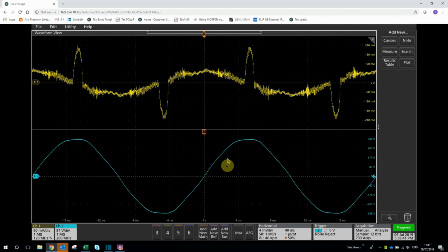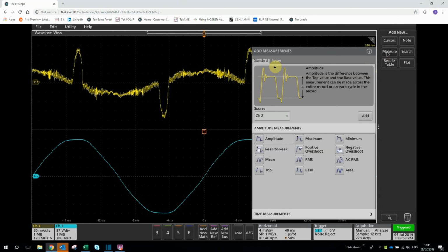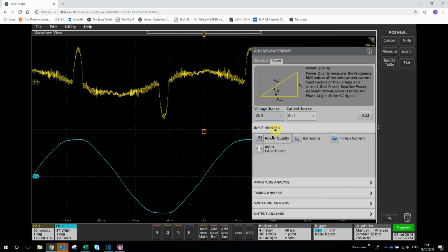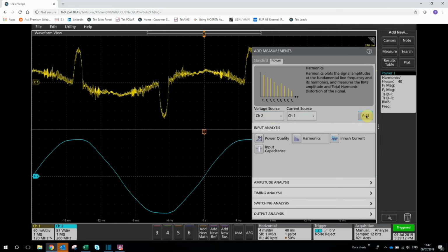the scope. Okay, so now that we've probed the inputs there, we can see that we've got our voltage source here on channel 2, and our current waveform there on channel 1. So to take this measurement, let's come over here to the right hand side and click measure. This opens up the measurements menu. This is going to be a power measurement, and this is going to be input analysis of the harmonics, as we've said. So making sure our sources are set right, so voltage on channel 2 and current on channel 1, as we've said. So that's great. So clicking on harmonics there and pressing add gives us the measurement.